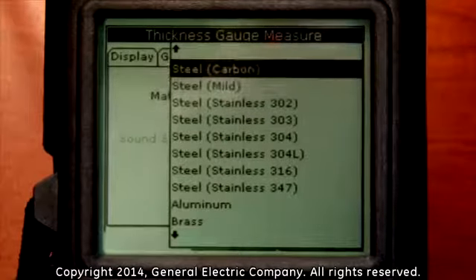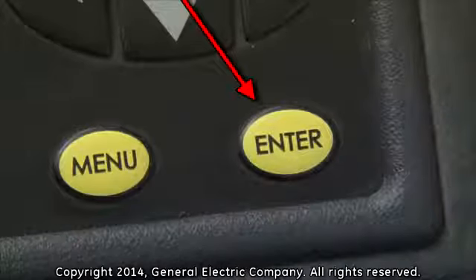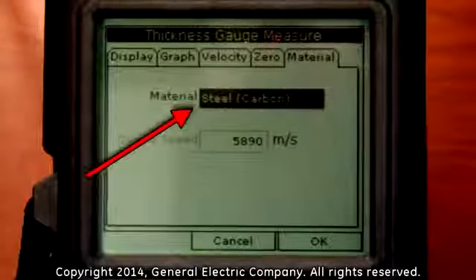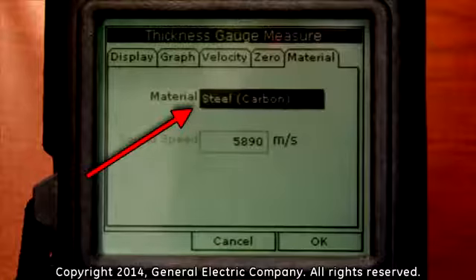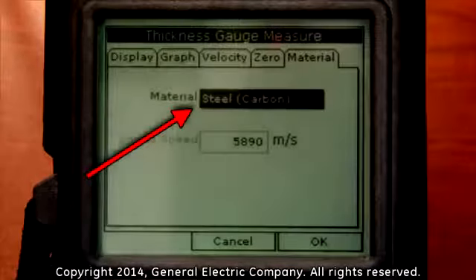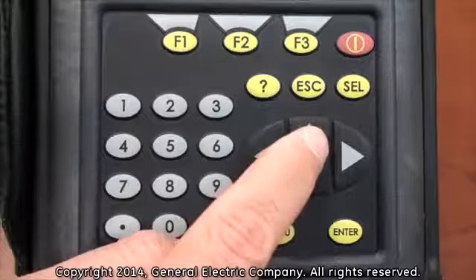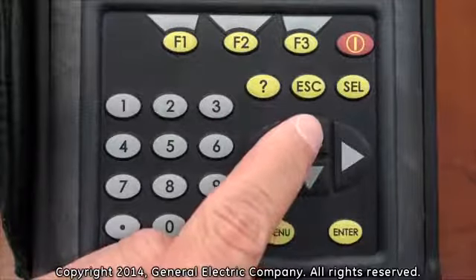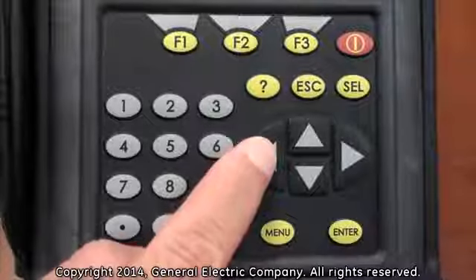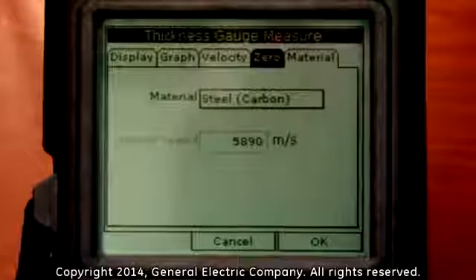When you have your material highlighted and selected, press the Enter button on the keypad. You will now be taken out of the Material drop-down menu and back to the Material tab. You will see the material you selected in the material field. In this case, it is carbon steel. Now press the up arrow on the keypad to go back up to highlight the Material tab. Then use the left arrow key to navigate over and highlight the Zero tab and press the Enter button on the keypad.